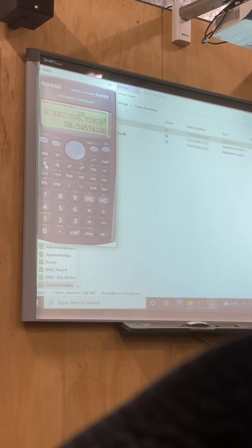Is this for CS? Okay, the cable is installed for ground. No. What we're working on then, sorry? We've just worked out the IT. Yeah. So we now need to look at the cable current carrying capacity tables and see which cable will be suitable for carrying this current. And it's 70.2 amps, is that right? 70.2 amps. So when looking at that table, can you all see it? Which one, sorry? The top one, bottom one? The bottom one, page 409.